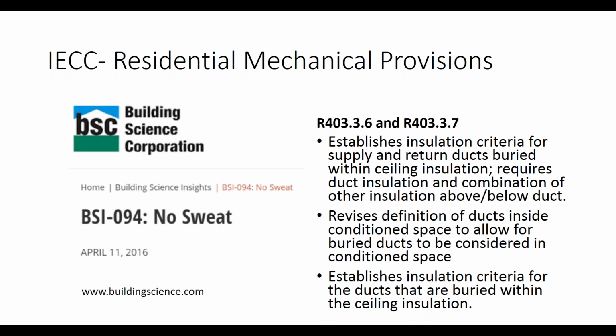So how can I put my duct in the cavity and still meet the requirements? Or how can I have my ducts be considered inside the conditioned space even if they're in the attic? These are things these new sections are dealing with. You can put your duct in there, but you have to put a certain amount of insulation on the duct, a certain amount of insulation below the duct, and a certain amount above the duct. There are very specific requirements if you want to call it inside conditioned space and still meet your duct insulation requirements and your ceiling insulation requirements.